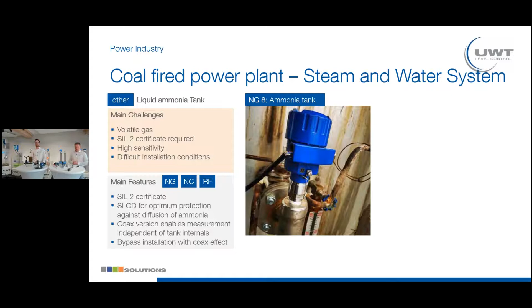So we have also one specialty here, the SLOD, the second line of defense. And this is the optimum protection against diffusion of ammonia, because it's a very small gas that likes to go out. So we need to have a protection against this diffusion. This is the second line of defense. Bypass installation, perfect for the Nivo Guide. You could also use a coax probe here, and many options. You get the same effect with a bypass as with the coax, so the energy is more focused inside those small coax tubes or inside the bypass, so you get even more accurate and more reliable measurement results in those types of installations. All right, good.